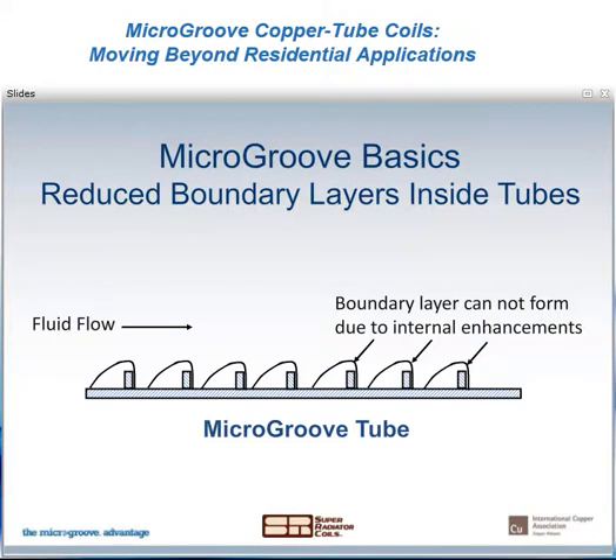MicroGroove tubes with internal enhancements reduce the formation of boundary layers. And this illustration shows how the boundary layer begins to develop, but it breaks down as it moves over the grooves. The additional mixing of the refrigerant that occurs inside the tube because of these grooves increases the amount of refrigerant that comes in contact with the tube wall. The positive effect of heat transfer from these internal enhancements has been known for a long time, and it's been also applied commercially for a long time. But what's new more recently is a combination of internal tube enhancements with small diameter tubes.